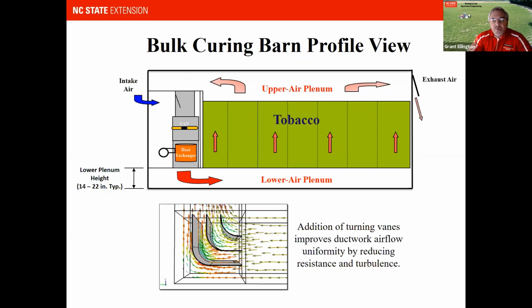And so this is showing what a turning vane looks like, and it is a simple sheet metal structure that is added to, instead of having that 90-degree abrupt change, now we can gradually have that airflow change directions. And so addition of turning vanes is going to improve the ductwork airflow, once again uniformity, and it does this by reducing the resistance and turbulence associated with if you did not have a turning vane in the ductwork. And once again, this is a very common application in the HVAC industry.